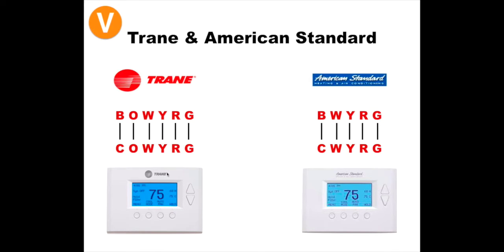The reason we want to identify these is Trane American Standard does things a little differently. They don't have C wires on their thermostats, they don't use C for the 24-volt common like we do. They use the B terminal instead. So the main rule to remember for Trane American Standard is: B goes to C. If you remember that, it will save you a lot of headaches.